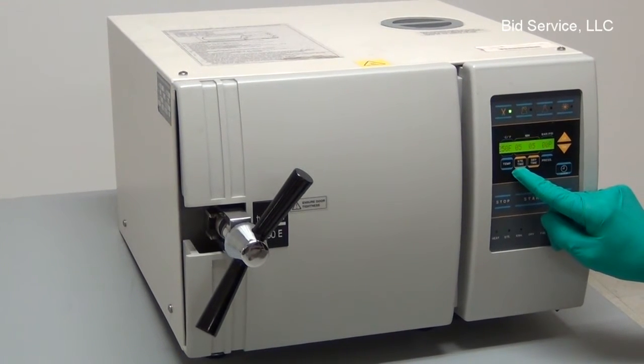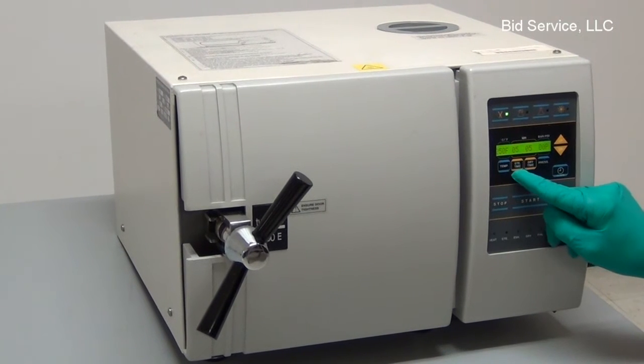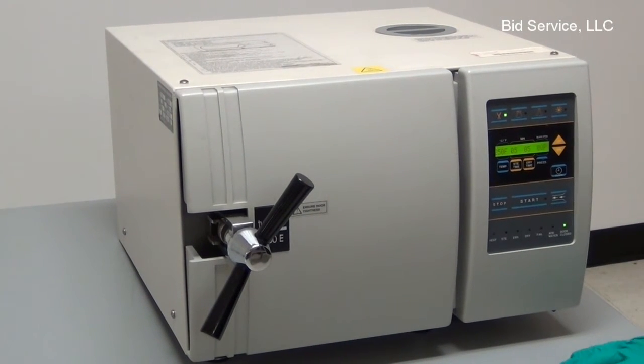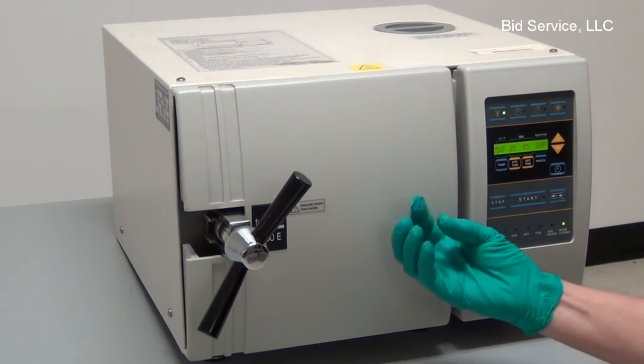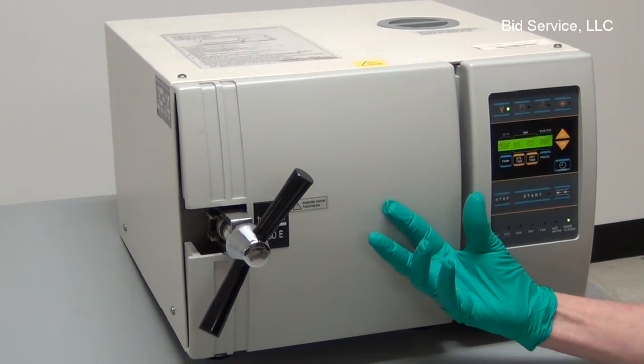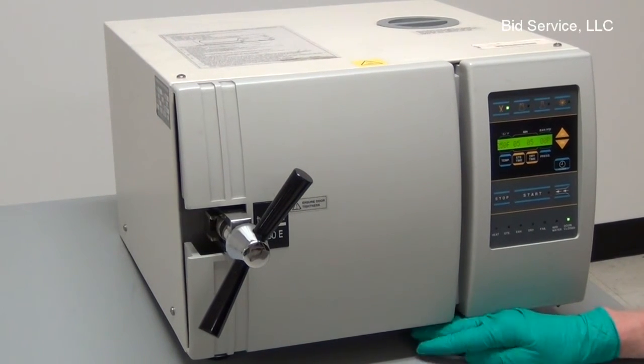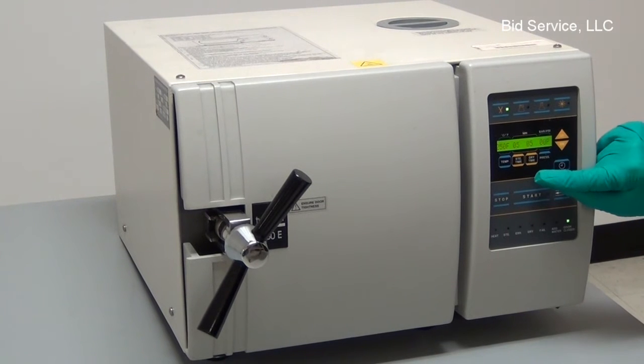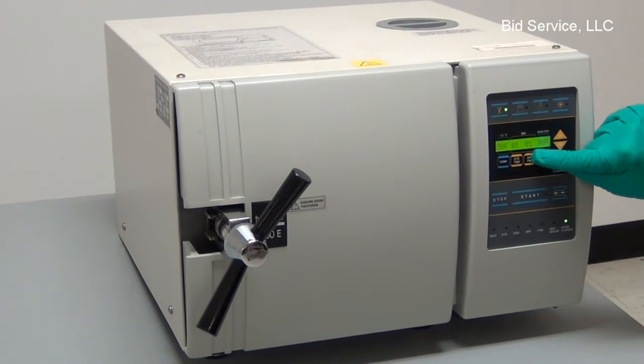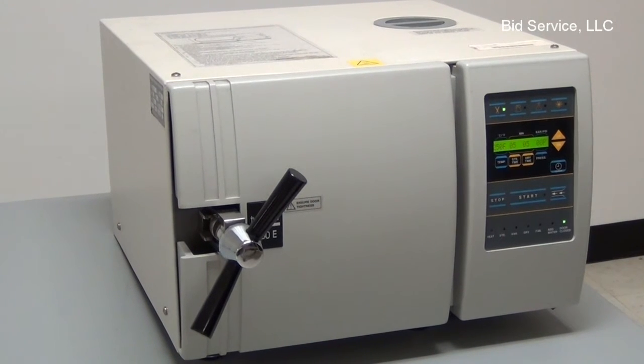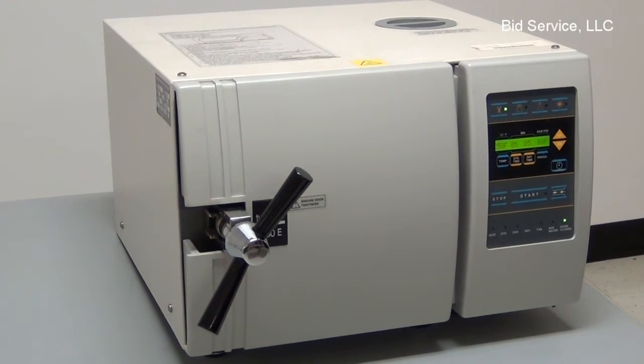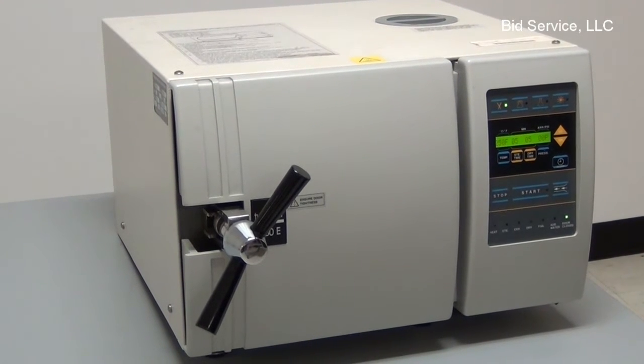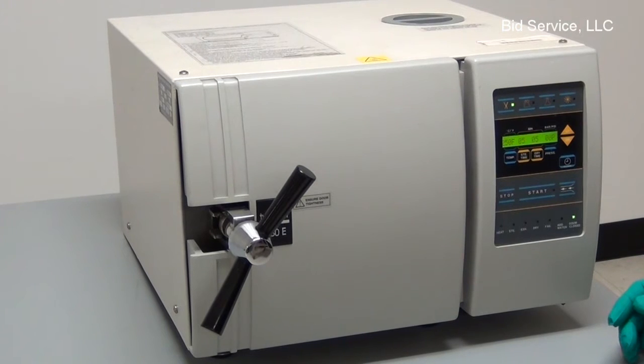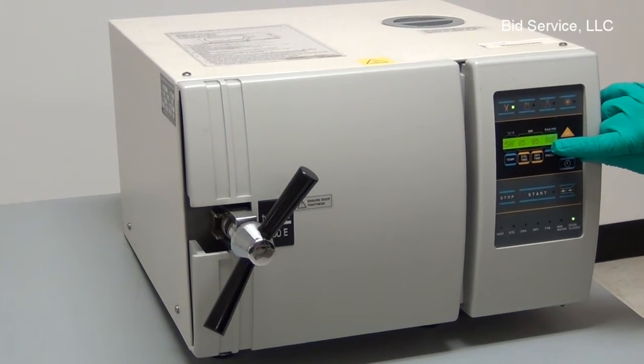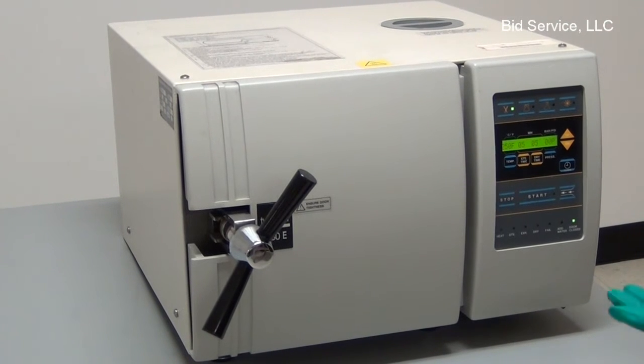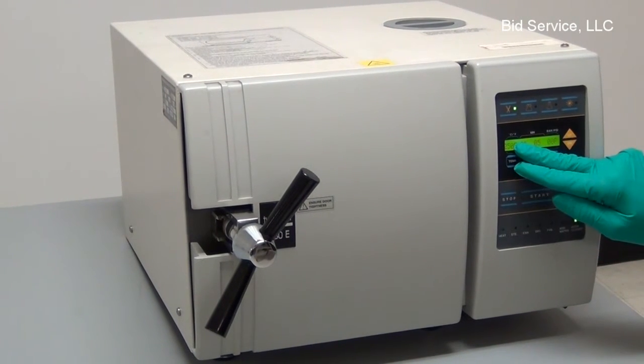The next cycle after sterilization would be the drying time. The drying time is also accompanied by an automated exhaust. What this actually does is take the steam pressure that was originally used during sterilization and exhaust it out of the chamber. After that, there is a drying time partial cycle that will then allow it to dry completely, to try to exhaust as much humidity as possible, and then it will signal that the cycle has been completed. If for some reason you don't have the correct pressure within the range of what you're sterilizing, you will get an error that shows you have the wrong pressure.